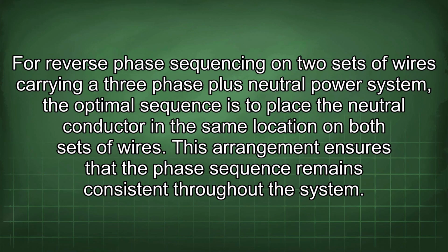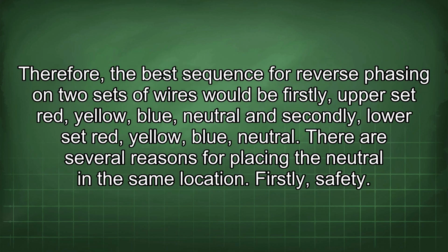For reverse phase sequencing on two sets of wires carrying a three-phase plus neutral power system, the optimal sequence is to place the neutral conductor in the same location on both sets of wires. This arrangement ensures that the phase sequence remains consistent throughout the system. Therefore, the best sequence for reverse phasing on two sets of wires would be firstly, upper set red, yellow, blue, neutral, and secondly, lower set red, yellow, blue, neutral.